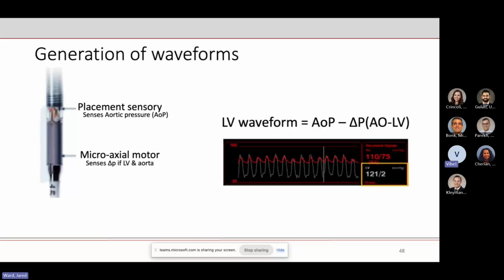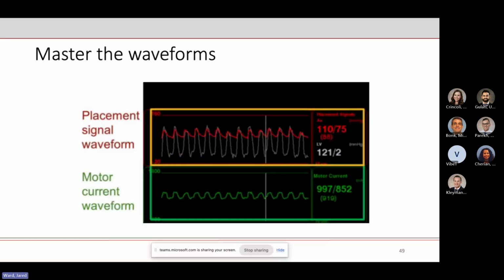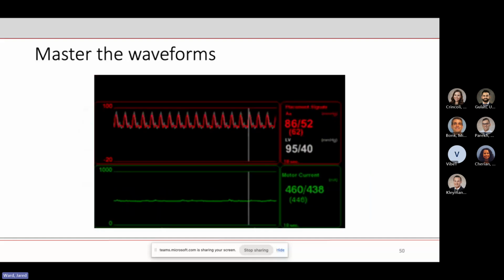The red value is just generated off of an arterial line. So this is basically what a normal, normally functioning Impella should look like. And because the signals have to be generated with differences across pressures, the two most easy to diagnose waveforms are when they're flatline, right? With the motor current, there's no current going across because the sensors are in the same place.